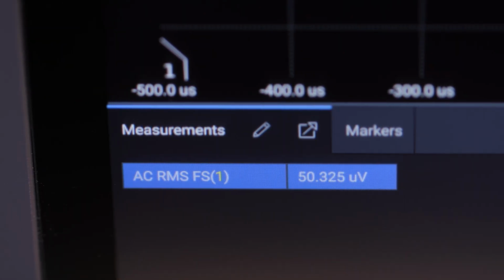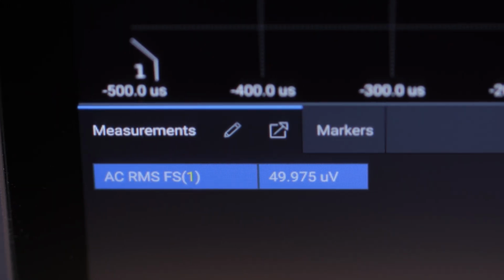When testing power supplies, every microvolt matters. With microprocessors and microcontrollers using less and less power, the power supply levels required in the industry have moved from 5 volts a decade ago to just 0.9 volts today. And so small ripples and glitches, which were immaterial at 5 volts, can now be the source of errors that cause device crashes, reboots, and more.